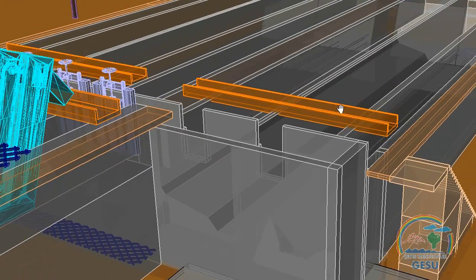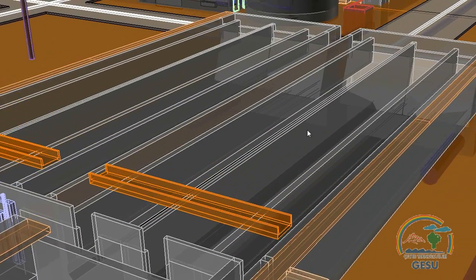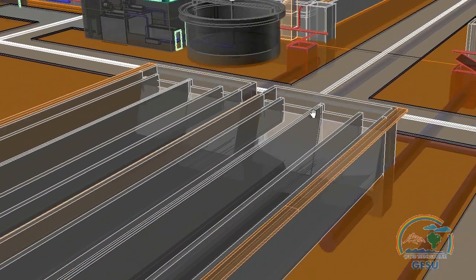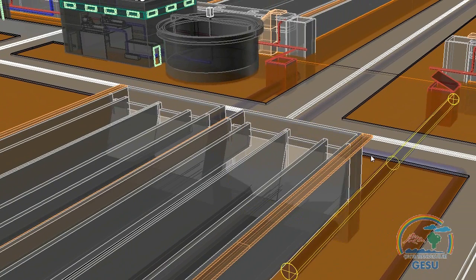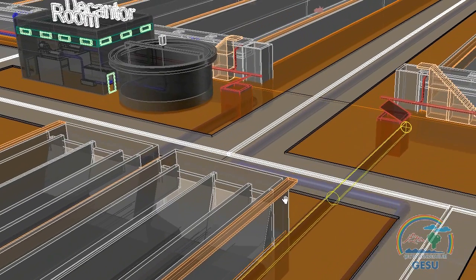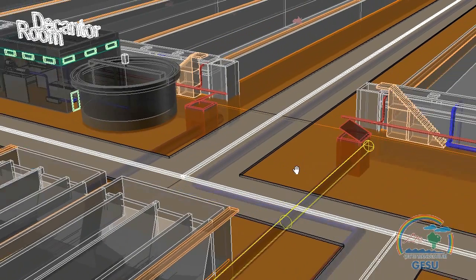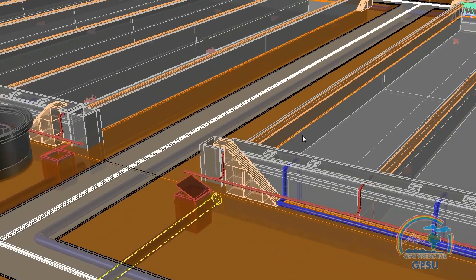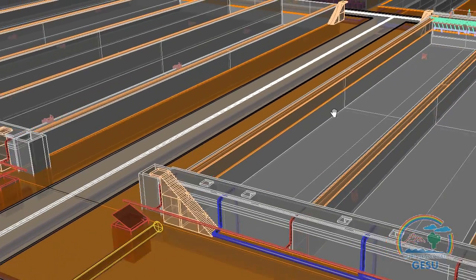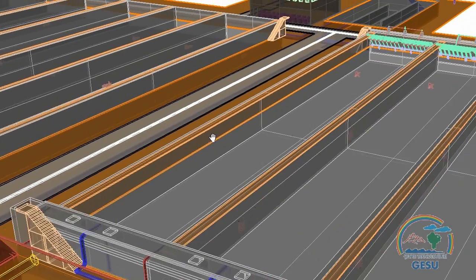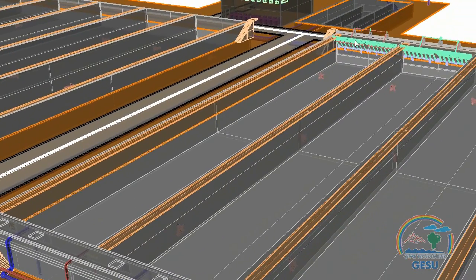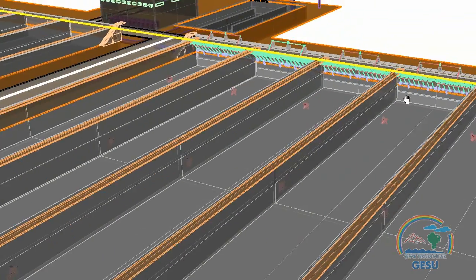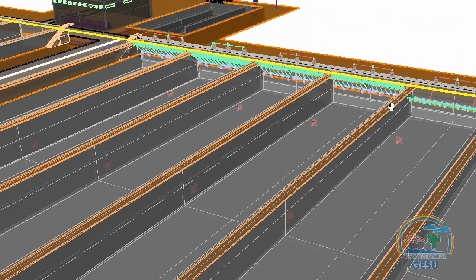Water passes through pen stocks and comes to the grit chamber unit. In this unit, grit particles settle at the bottom of the tank and oil and grease are skimmed off with scrapers. Wastewater is then transported via a 1-meter diameter pipe to the SBR reactors.